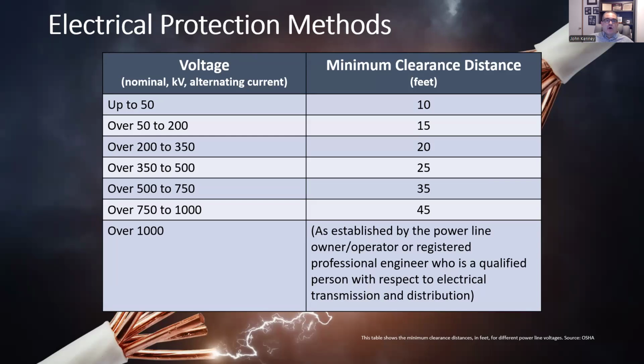Electrical protection methods. For voltage up to 50, minimum clearance is 10 feet. 50 to 200 is 15 feet. 200 to 350 is 20 feet. So on and so forth. And you can see, with a high voltage power line, 750 to 1,000, you're at 45 feet of clearance. Over 1,000, that's a transmission station, and you probably need to contact the power company for safe distances. You should always verify with them anyway what you're working around. But this gives you an example of how dangerous electricity can be where we work, and how far it can travel.